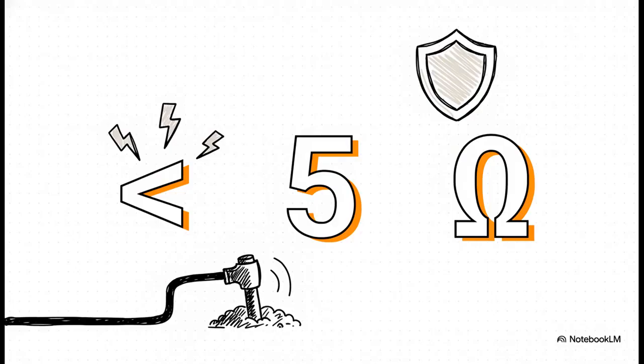And that professional verification brings us to a magic number. According to Indonesia's General Electrical Installation Requirements, or PUIL, a residential grounding system must have a resistance value of less than 5 ohms. That number is the official benchmark for safety.